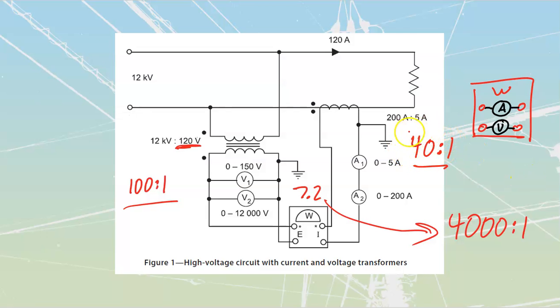Same with these ones over here. If it's a 40 to 1 ratio, I'm able to read what that would be based upon what I've got coming through here. If I take a look at this 0 to 5 amp over here, let's say it's coming in at 3.5 amps right now. We'll ignore this one. We'll pretend like we can't read that. Otherwise, we would just read it directly off of it.